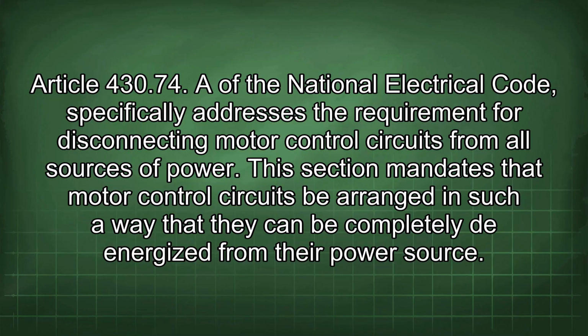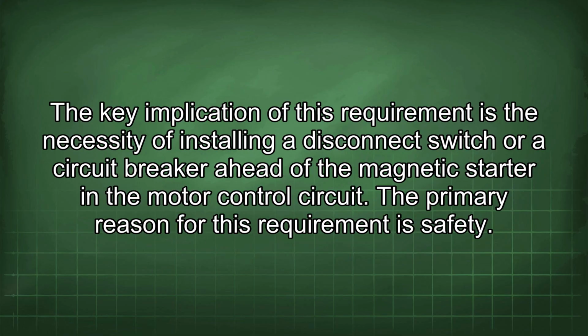Article 430.74 of the National Electrical Code specifically addresses the requirement for disconnecting motor control circuits from all sources of power. This section mandates that motor control circuits be arranged in such a way that they can be completely de-energized from their power source. The key implication of this requirement is the necessity of installing a disconnect switch or circuit breaker ahead of the magnetic starter in the motor control circuit.